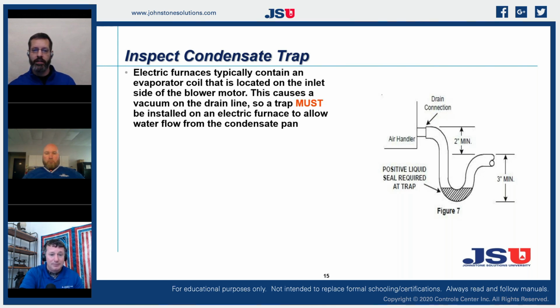Well, as we start moving, or have moved, into ECM motors, they're going to ramp up if something happens. And if you get too strong of a negative pressure because the blower motor is running hard, you'll actually suck that thing dry and overcome it. So you do need to have a 2-inch minimum or a 3-inch minimum. Overall, usually it's a 5 to 6 overall that manufacturers want total. That's right. That is important.